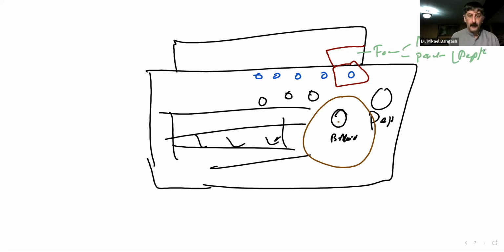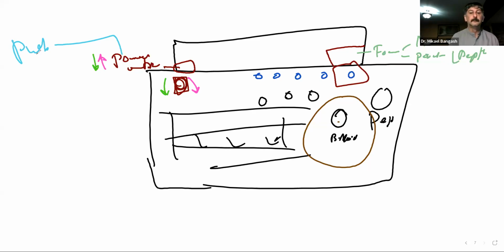But I also said over here was a knob, and the function written to this was power output. By turning that clockwise, that will increase the power output, or turning it anti-clockwise would decrease the power output, which was controlled by the pulsar. Likewise, increasing the depth will lead to an increase in the PRP and a decrease in the PRF, or the other way around.